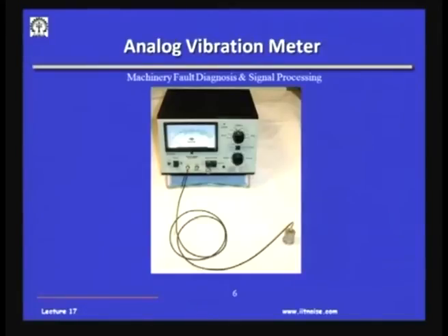But if you go to the earlier days, we had this analog vibration meter, and this is what it looked like. So, this is the accelerometer which I was just talking about. This is a uniaxial accelerometer. The piezoelectric crystal is inside this, okay, and this can withstand very, very high temperatures, may as well go up to about 200 degrees Celsius or 300 degrees Celsius. This is shielded from moisture, humidity, rain, etc. And then this cable, because as soon as the charge is produced, we will go to the details of the vibration transducers regarding the mounting, etc. in the subsequent classes.